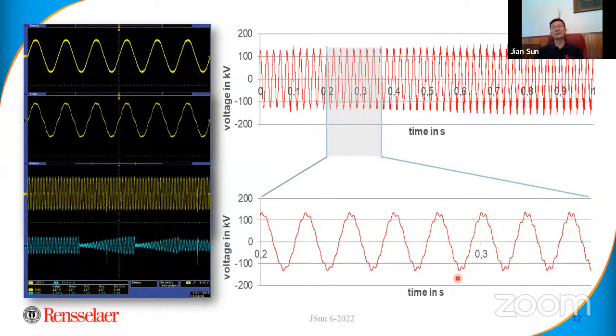There was actually a major incident in the German North Sea because of this kind of resonance. It caused a fire in an offshore HVDC station, you may have seen some pictures of it, I actually have a picture of that. One of the stations caught fire internally, which burned down a large section of the converter system. That was a major incident.